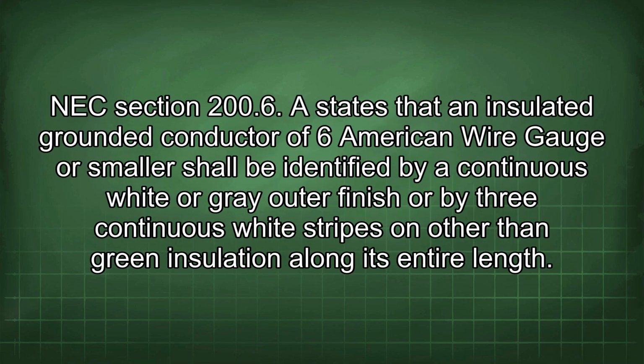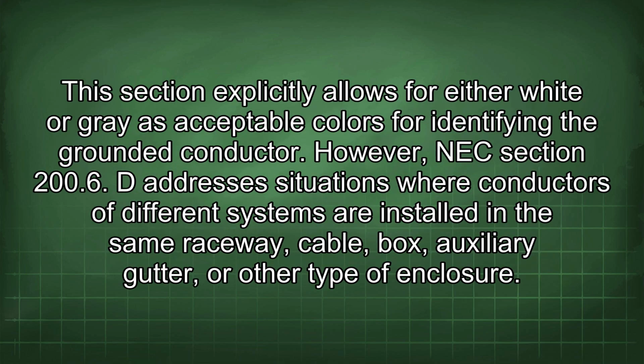There are specific sections within the NEC that address the identification and use of grounded conductors. NEC Section 200.6 states that an insulated grounded conductor of 6 American wire gauge or smaller shall be identified by a continuous white or grey outer finish or by 3 continuous white stripes on other than green insulation along its entire length. This section explicitly allows for either white or grey as acceptable colors for identifying the grounded conductor.